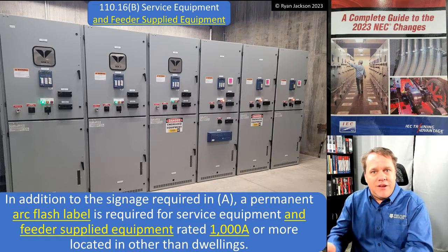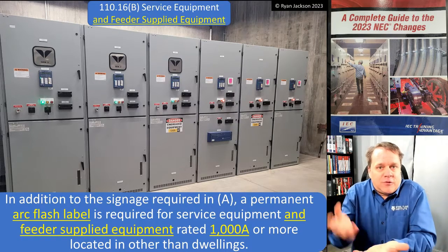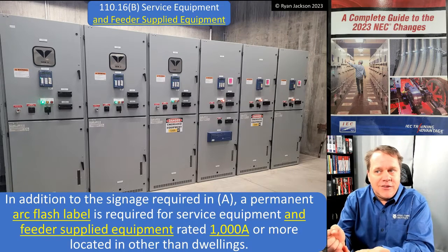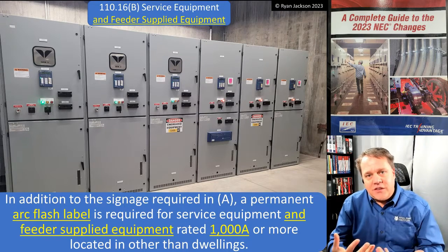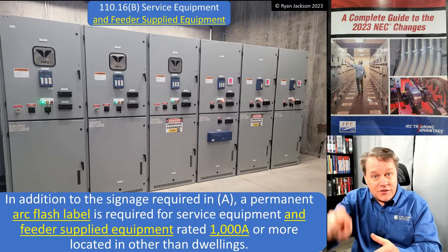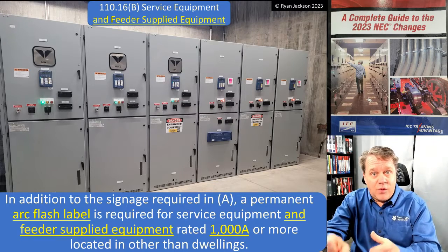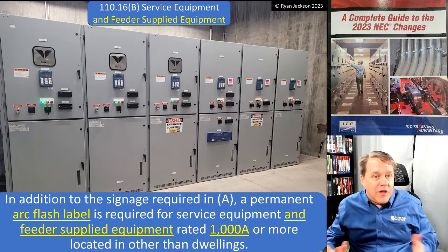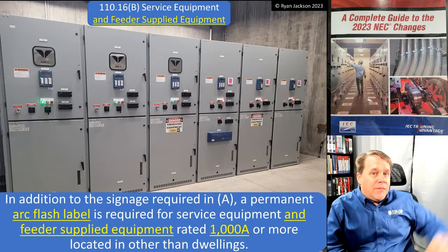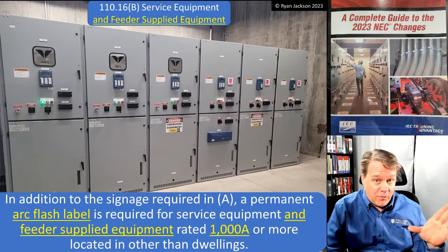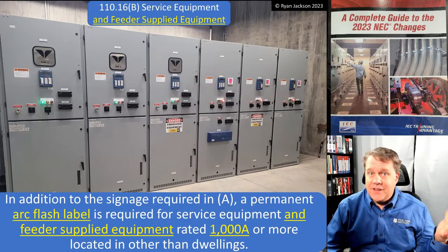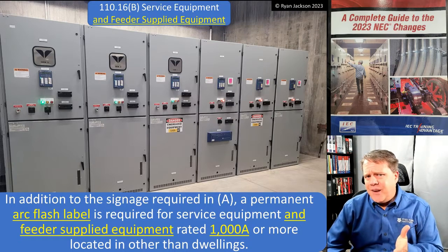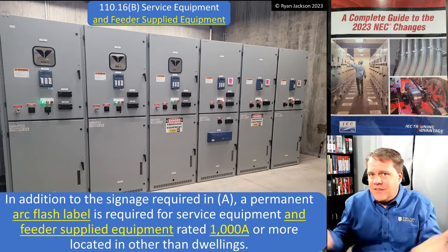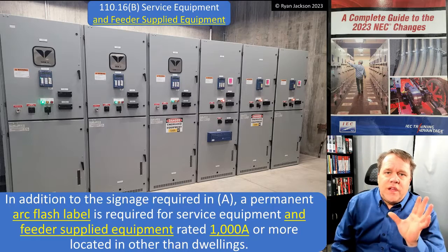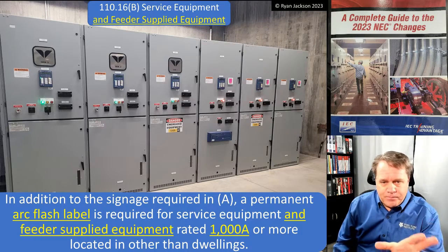The service equipment is the first place, that's the first breaker or fuse, right? So if you're in the service disconnect and the service disconnect breaker trips, guess what? The arc flash is still happening. You got to wait for the utility primary on the pole to cut open. And that might take next week. So it was kind of dumb to say you got to mark the clearing time, because that doesn't make any sense. So they changed that, and here's what it says now.